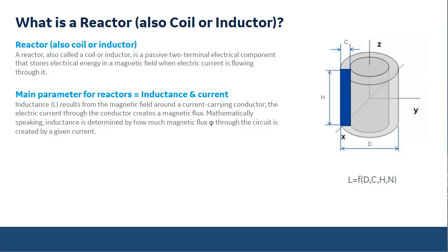Okay, so what do you need to tell us if you want us to size the correct size of reactor or if you want an offer for it? Basically, we need to know the current, the voltage, the power rating, which is calculated based on the current, voltage and impedance, the application, and the conditions that these reactors are going to be installed at. Just quick on each one of these, current. The current will impact the size of the conductive material, or basically the cross-section. More current means that you need more cross-section, you need more area to conduct that current.